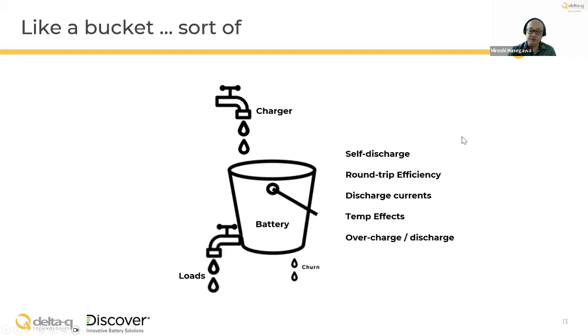Temperature effects: low temperature results in less overall capacity but better overall battery life, whereas high temperatures let you extract more capacity with the trade-off of less overall life. Some technologies are more sensitive than others. Lead acid is generally more forgiving with a wider operating and charging temperature range, while lithium doesn't do well in extreme temperatures, and the BMS tends to restrict charging below 0 degrees Celsius.